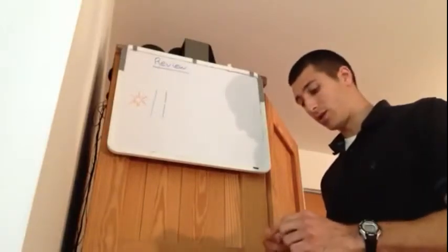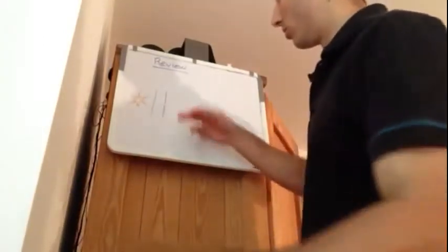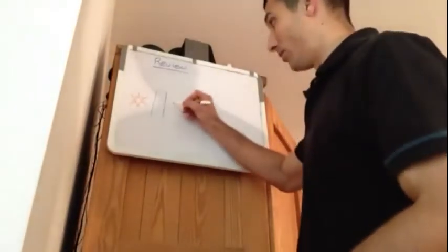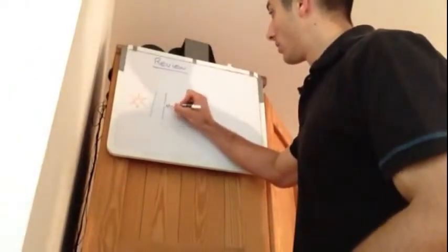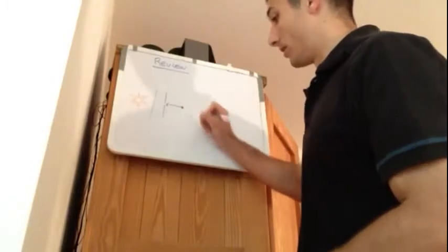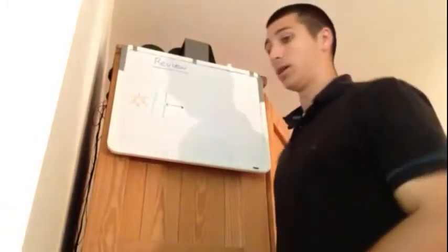So now we have electrons accelerating towards the anode plate, and we left a small hole here in the middle of the anode plate where electrons can then pass through the plate, and they'll come out on the back side as our electron beam. So that's our first component, the electron gun, creating our electron beam.